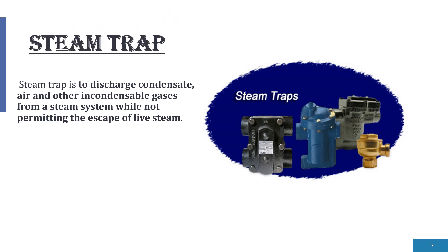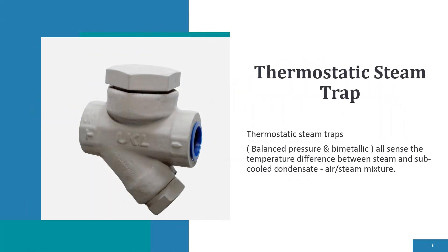Let's move on to the next topic: steam traps. A steam trap is designed to discharge condensate, air, and other non-condensable gases from a steam system while not permitting the escape of live steam. One type available is the thermostatic steam trap, which senses the temperature difference between steam and sub-cooled condensate, air, or steam mixture.